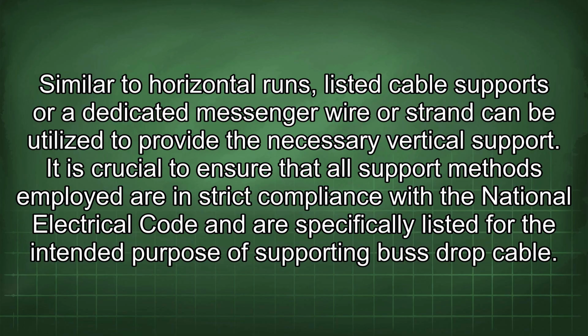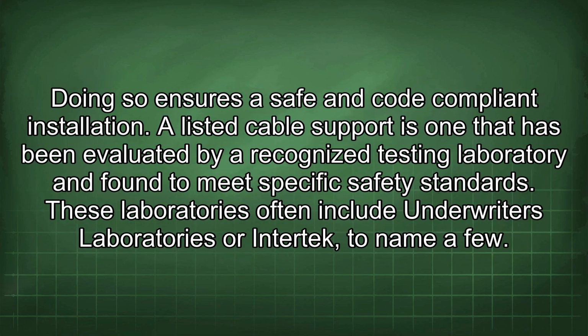Similar to horizontal runs, listed cable supports or a dedicated messenger wire or strand can be utilized to provide the necessary vertical support. It is crucial to ensure that all support methods employed are in strict compliance with the National Electrical Code and are specifically listed for the intended purpose of supporting bus drop cable. Doing so ensures a safe and code-compliant installation.